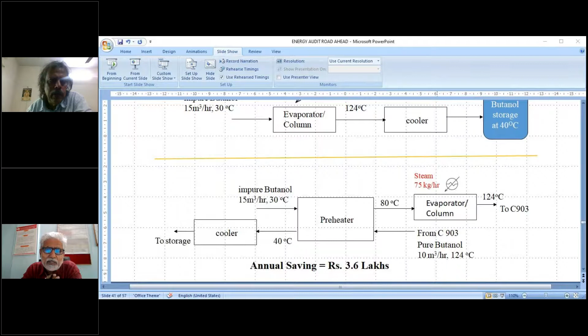If you want to exchange that heat, the delta T matters. Again it will come to maybe 40, 45 degrees Celsius maximum. Sometimes it may not be economically viable. It is better to waste some heat rather than trying to fully utilize it all, because the economics will not permit it.